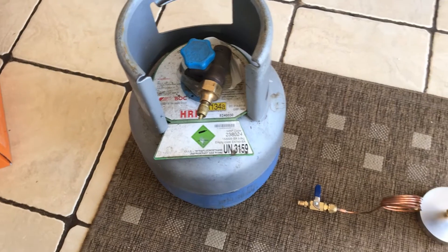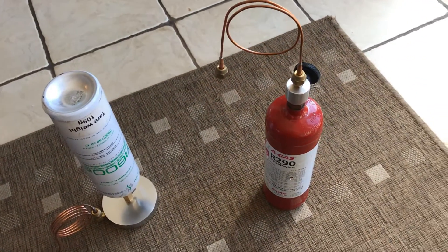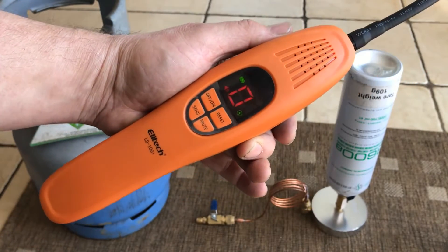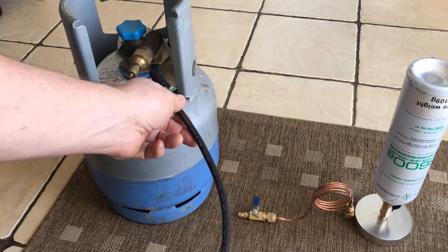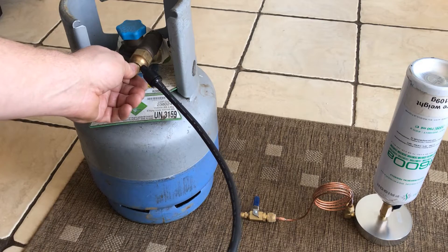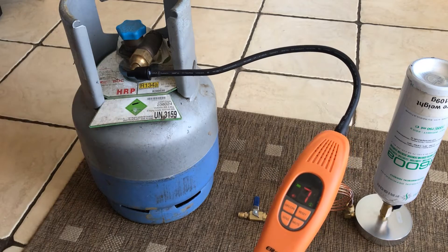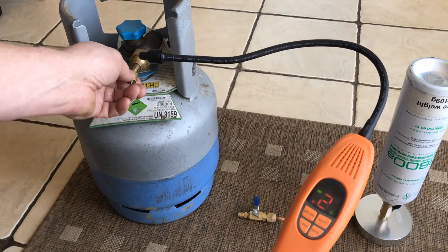I'm going to do a control test on three refrigerants: R290, R600a, and R134a. Starting on green — the lowest sensitivity — we come around to the R134a. I've released a tiny bit of refrigerant into the cap. Releasing the cap, we can see the Elitech has detected it straight away. The higher the number, the higher the concentration. No problem at all with R134a — fantastic.